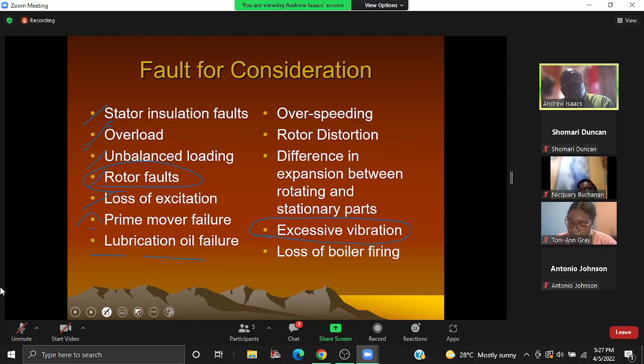So, you know, it's always rather interesting when we speak to excessive vibration, because if you go into a power house, if you're going into a generating facility, it's not exactly quiet, or neither is it still. Right? But we do note that given the speed at which the rotor is turning, any damage to that rotor, even a hairline fracture, will cause vibration above the normal, all right? And so we would know that those problems exist.